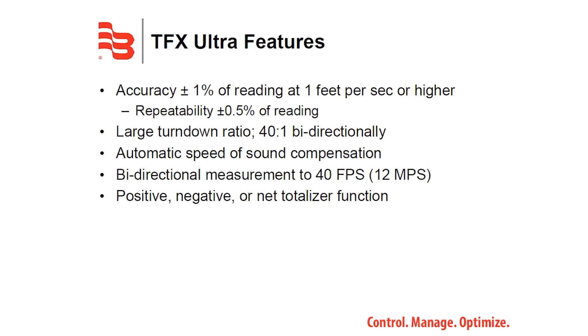The TFX Ultra offers repeatability of plus or minus 0.5 percent of reading, a large turndown ratio of 40 to 1 bi-directionally, automatic speed of sound compensation, bi-directional measurement to 40 feet per second, and a positive, negative, or net totalizer function.